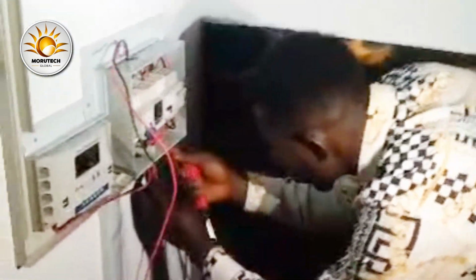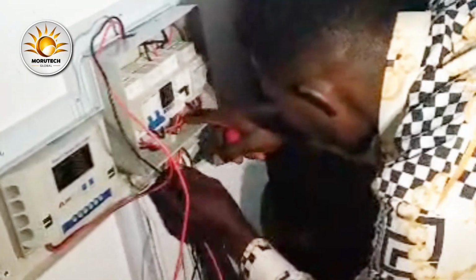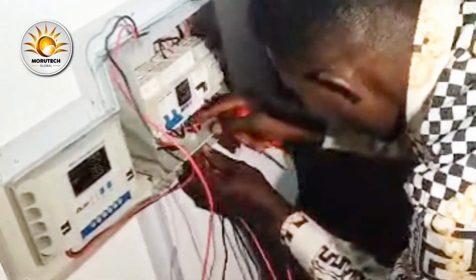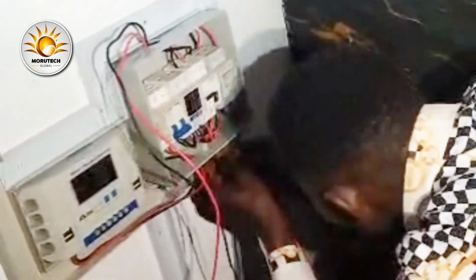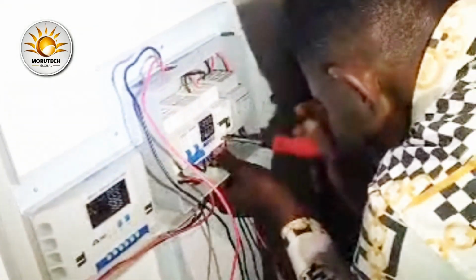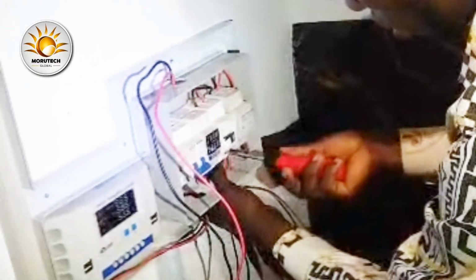Now I'm inside doing the internals. I've installed a 40 amp PWM charge controller and the combiner box. Inside the combiner box are our protective devices: the breaker, surge breakers, DC breaker, AC breaker, and the AVP, automatic voltage protector.